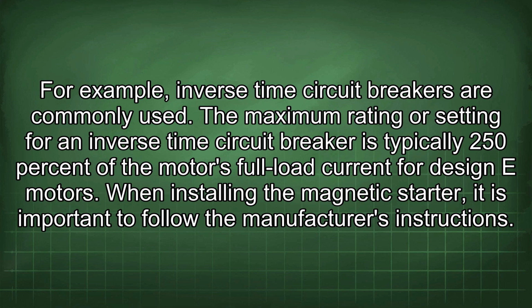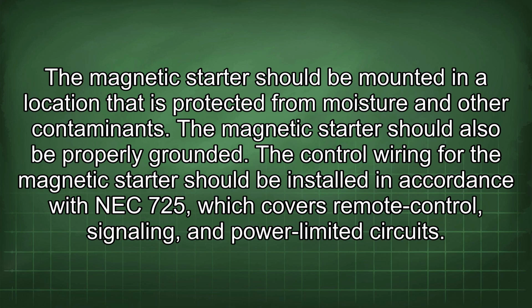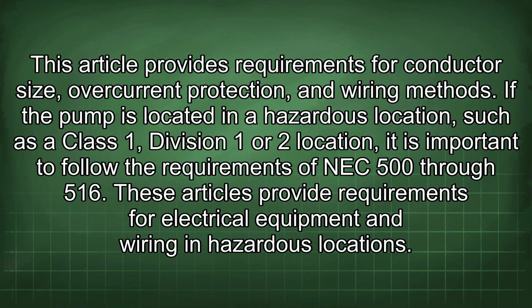for design E motors. When installing the magnetic starter, it is important to follow the manufacturer's instructions. The magnetic starter should be mounted in a location that is protected from moisture and other contaminants. The magnetic starter should also be properly grounded. The control wiring for the magnetic starter should be installed in accordance with NEC 725, which covers remote control, signaling, and power-limited circuits. This article provides requirements for conductor size, overcurrent protection, and wiring methods.